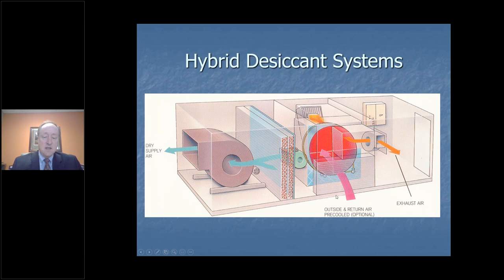So in this case, this particular unit right here has pre-cooling coils, pre because that means before, and that's before the wheel. That's the desiccant wheel. So let's let this air come in, again, outside air or return air, and it will dehumidify down to the coil dew point temperature. And let's say that's 55 degrees Fahrenheit. That's very easily done with coils.